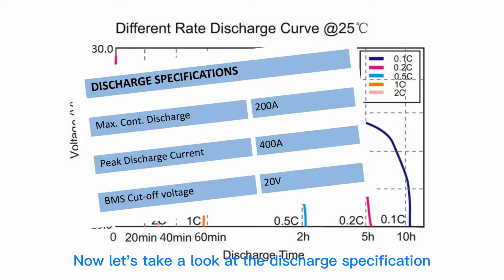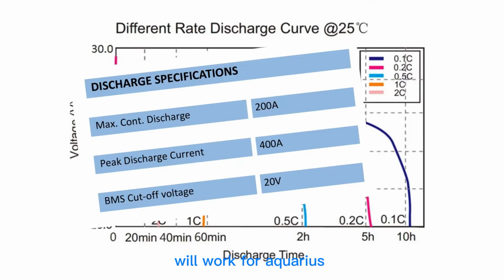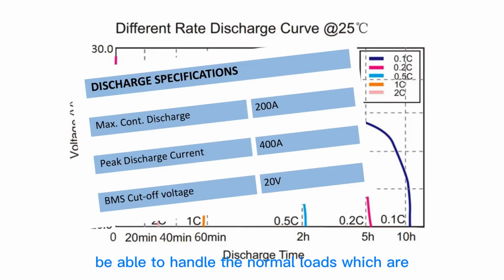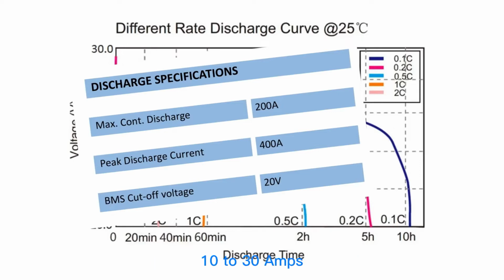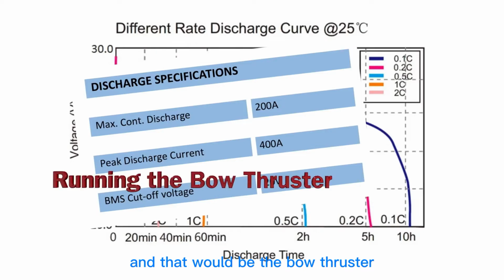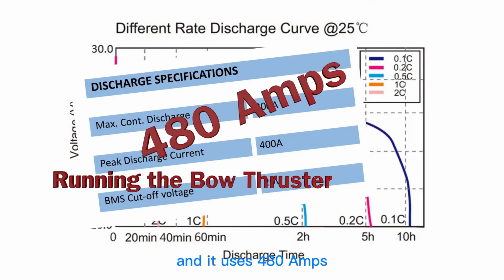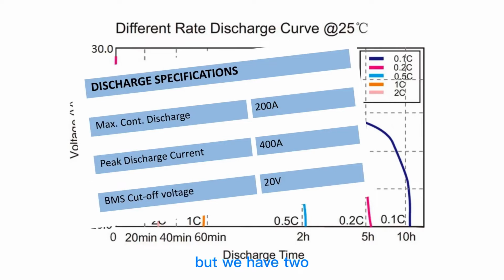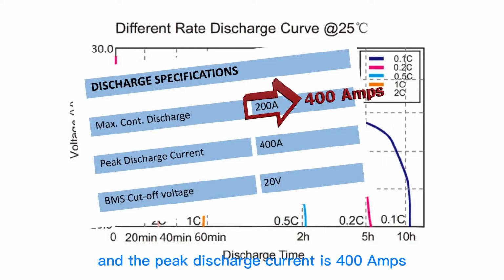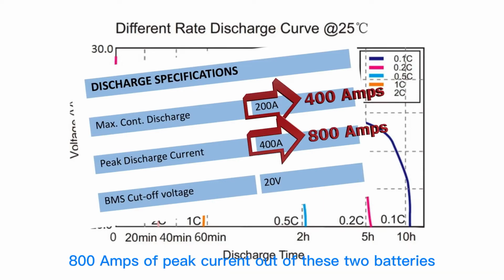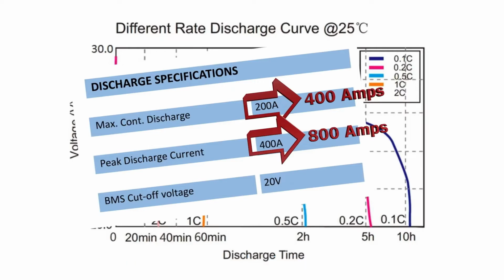Now let's take a look at the discharge specification. We just want to make sure that these two Lithium Valley batteries will work for Aquarius. Now, surely they'll be able to handle the normal loads, which are 10 to 30 amps. But let's look at the largest load, and that would be the bow thruster, and it uses 480 amps. The max continuous discharge for one battery is 200 amps, but we have two, so we have 400 amps. And the peak discharge current is 400 amps, and that gives us 800 amps of peak current out of these two batteries, and that surely will handle the bow thruster.